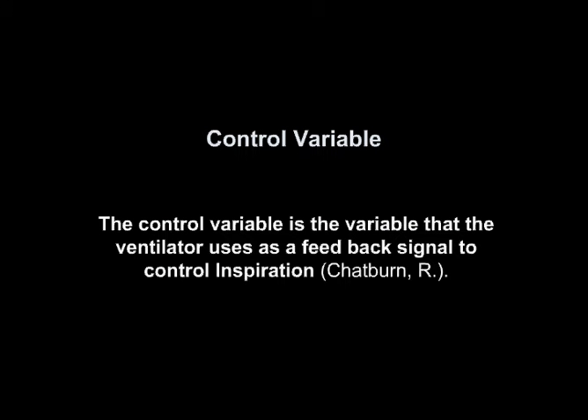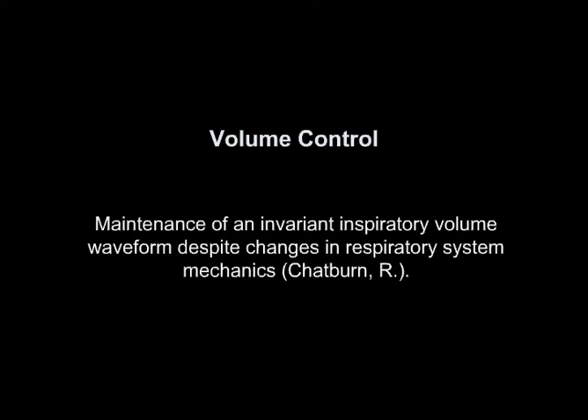A control variable is the variable that the ventilator uses as a feedback signal to control inspiration. With volume control, what the ventilator is trying to do is maintain an inspiratory volume waveform despite changes in the respiratory system.